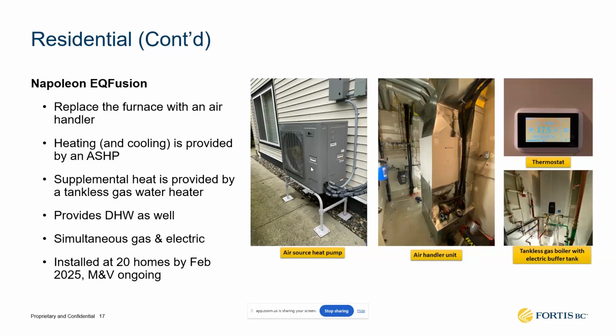Another advantage is that this tankless gas boiler will provide domestic hot water, and it can work in conjunction, as opposed to the furnace and the heat pump, where it can be one or the other. This can work simultaneously. So the heat pump will provide the heat at mild outdoor conditions, and when it's not able to keep up, it will start receiving additional heat from the boiler, and eventually at very cold outdoor temperatures, the heat pump will stop and the boiler will take over. We installed this system in 20 homes earlier this year, and it's been tested. It's going pretty well. We've had great acceptance from our customers, and we're expecting success with this technology too.